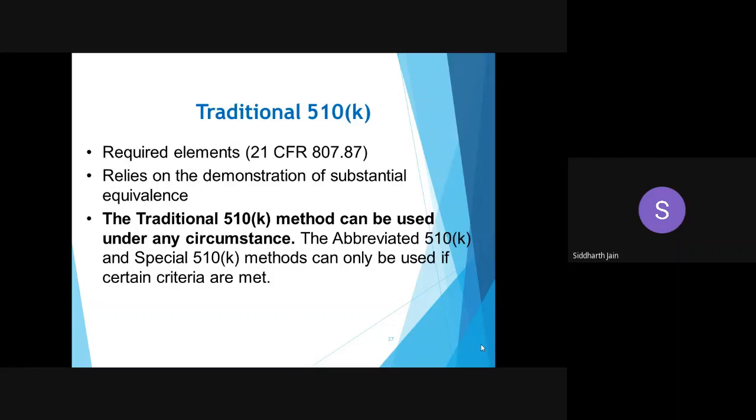The abbreviated 510K and special 510K methods can only be used if certain criteria are met. There are different types of 510Ks, as I already talked to you about. The traditional 510K is the most commonly used 510K method by medical device manufacturers worldwide. Next slide.